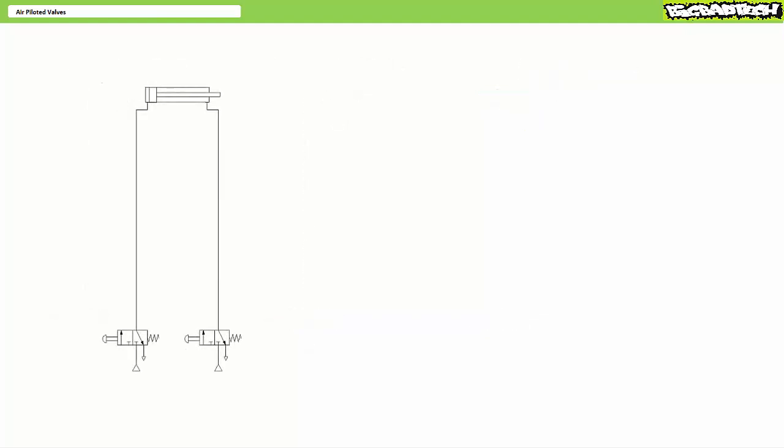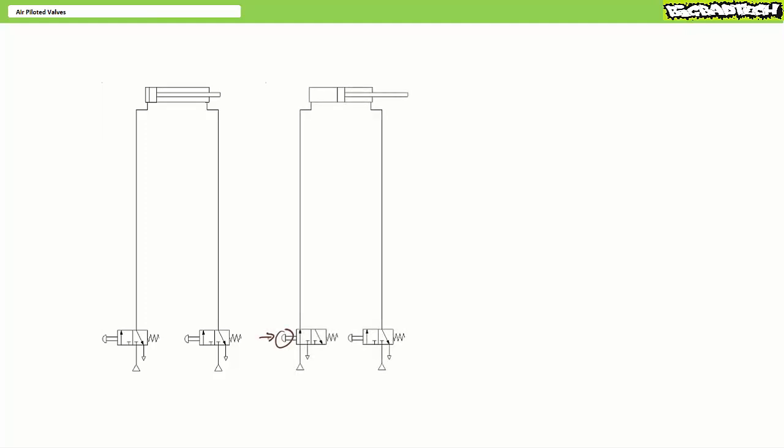As a means of reinforcing this point, consider a double acting cylinder directly controlled by two normally closed push button operated three by two directional control valves, both some distance from the actuator. When an operator presses push button one on the left, the cylinder does extend but extends slowly and weakly due to the pressure losses in the line feeding the cap end. To compound this poor performance, the line exhausting the rod end encounters a lot of resistance such that the cylinder is doubly slow and doubly weak. The same poor performance is experienced during retraction.